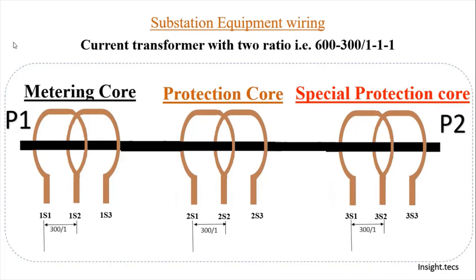Here, P1 and P2 represent the primary winding or the primary core, and to that we have three different cores. As discussed in the previous video, the secondary winding comes with three different cores in the current transformer. Here we have a current transformer with two ratios — 600 or 300 by 1 — meaning it can transform 600 amperes to 1 ampere, and also 300 amperes to 1 ampere. It has three cores: the first is the metering core, the second is the protection core, and the third is the special protection core.